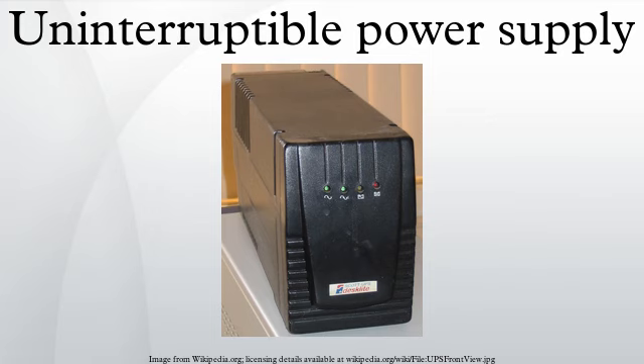This has become popular even in the cheapest UPSs because it takes advantage of components already included. The main 50/60 Hz transformer used to convert between line voltage and battery voltage needs to provide two slightly different turns ratios, one to convert the battery output voltage to line voltage, and a second one to convert the line voltage to a slightly higher battery charging voltage. The difference between the two voltages is because charging a battery requires a delta voltage.